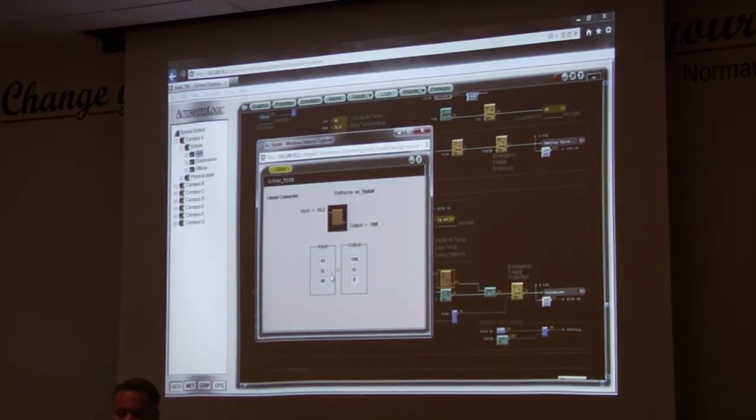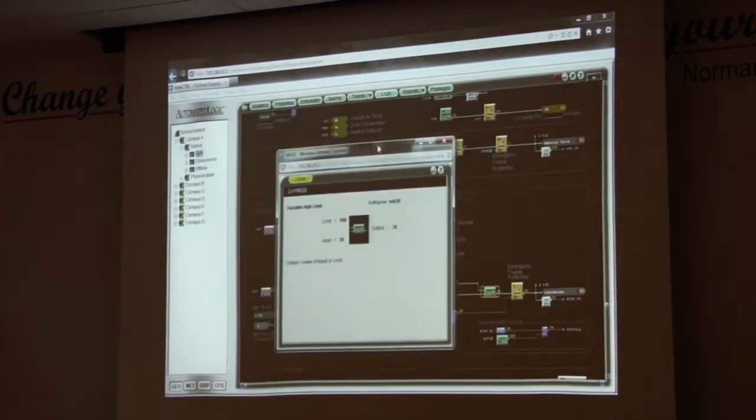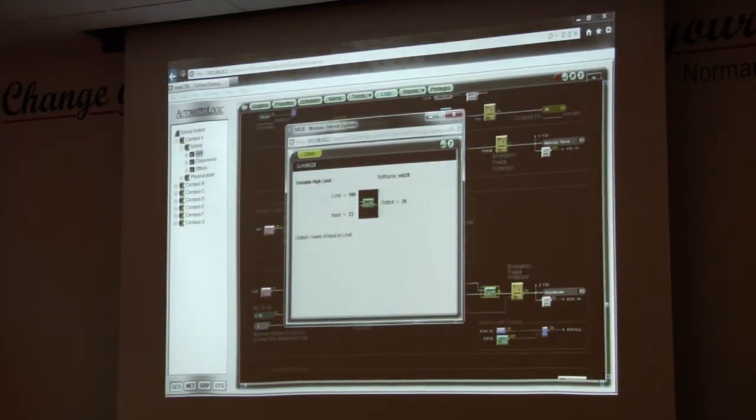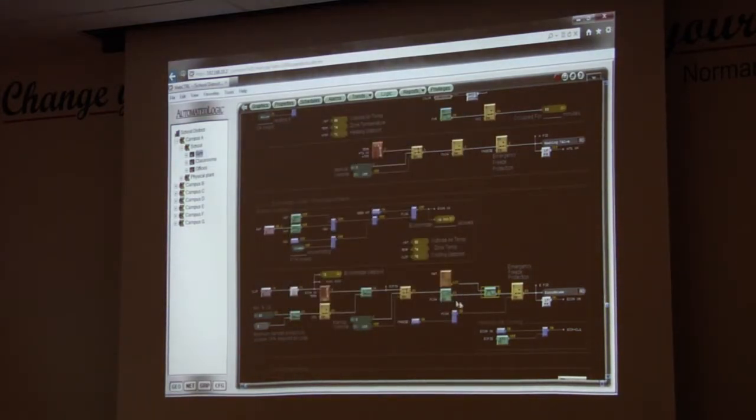Above, right? So now my limit is probably higher now. I don't know, I'm just guessing. But now it says 100, and I come down here, and look, my 20 is going through now. Let's look at this micro block. The limit now is 100, and how much am I giving it? 20, right? So that's less than 100, so that's fine. And now my economizer is going in.